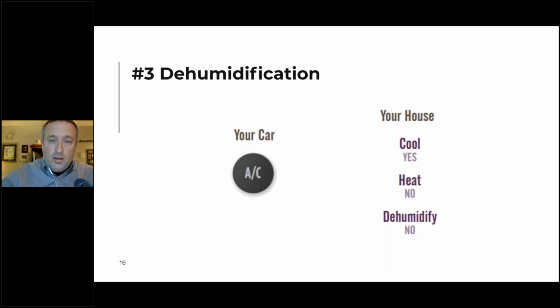Only when the air conditioner is on, and really only once it's been running for at least 10 minutes, do you get dehumidification. If your system is oversized, it may never run that long before shutting off. So humidity control in houses, in general, is not just terrible, it's abysmal.